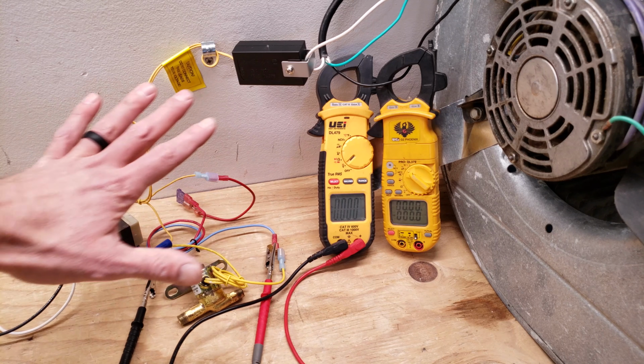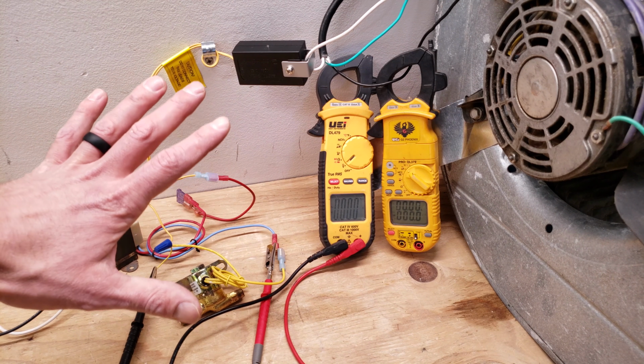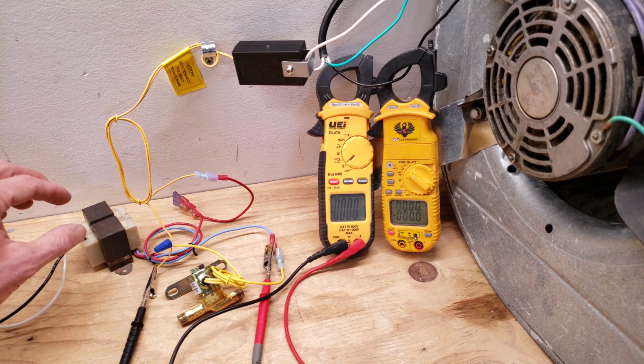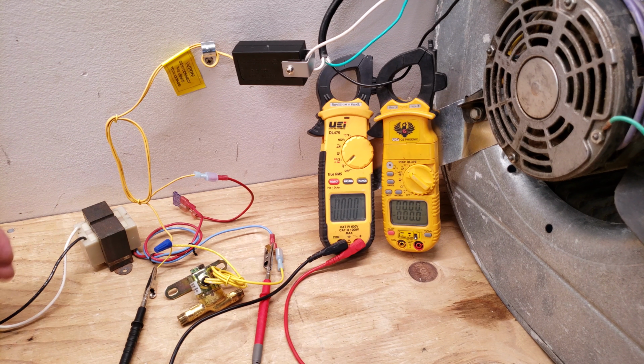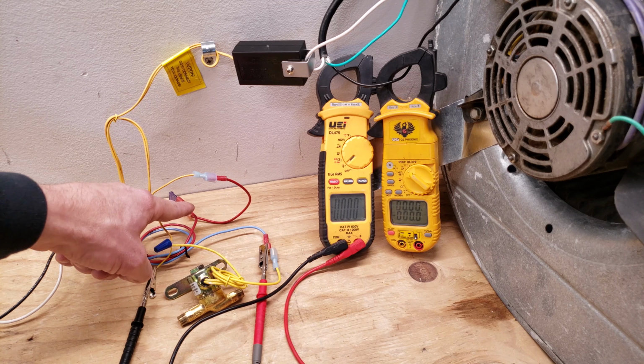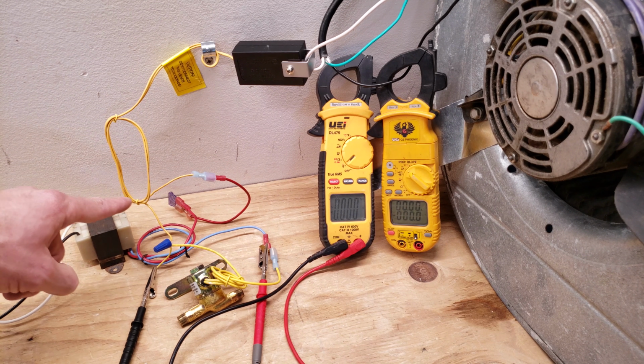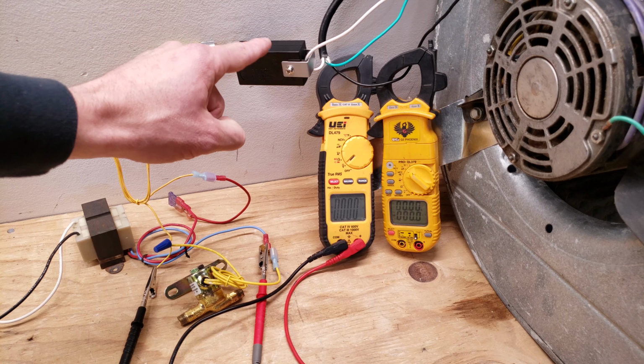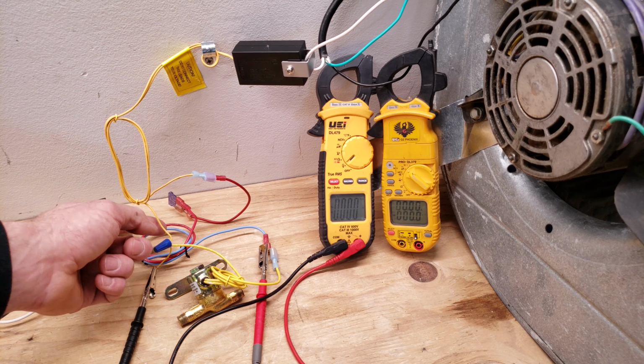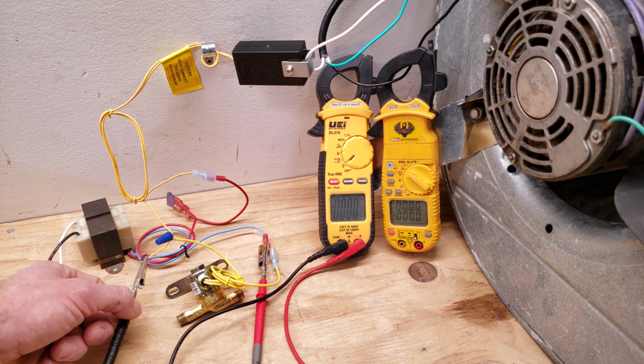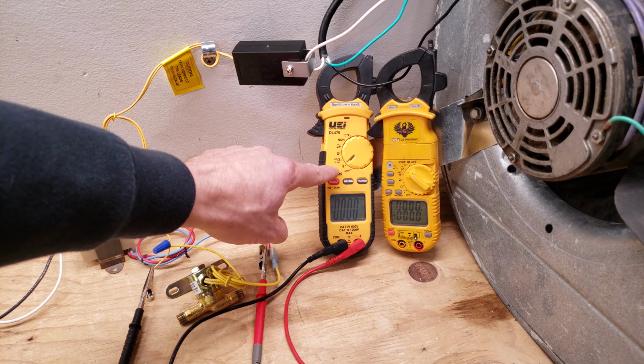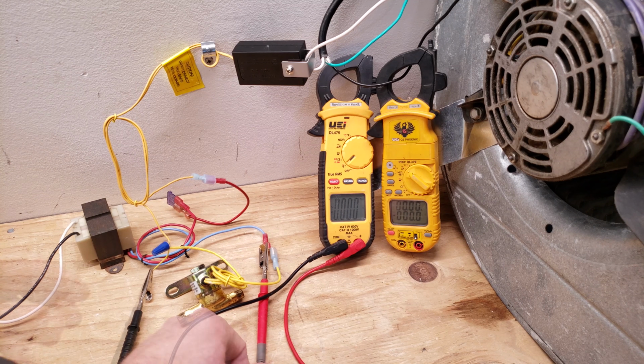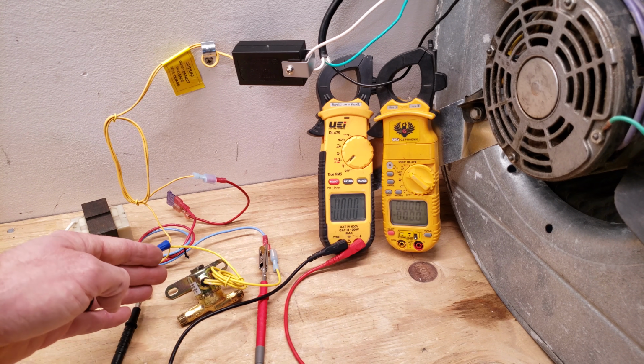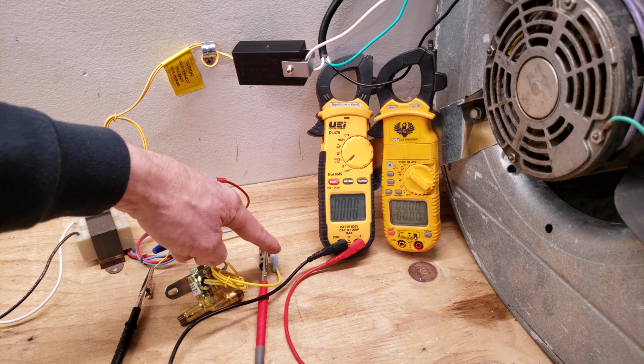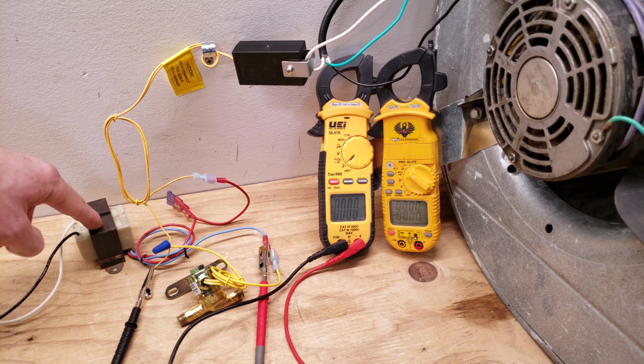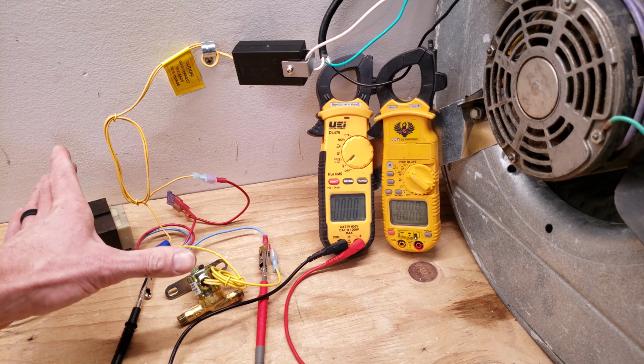So I'm going to show you what's happening with these wires here and why I have the multimeters set in the way I have them. So right here you have 120 volts coming into the transformer. However, I have the power off right now, and 24 volts comes in on that red wire, and it goes through that fuse. It goes over into the wire and over into this relay. Then it comes out and goes over to this wire nut. I happen to be taking a measurement right here with our multimeter. We're going to be measuring voltage on this and right here, so we're going to know if we have 24 volts on that solenoid there. And you always have to have a path back, which is called the common, and it goes back through that blue wire over to the transformer. So that's the 24 volt path that we have right now.